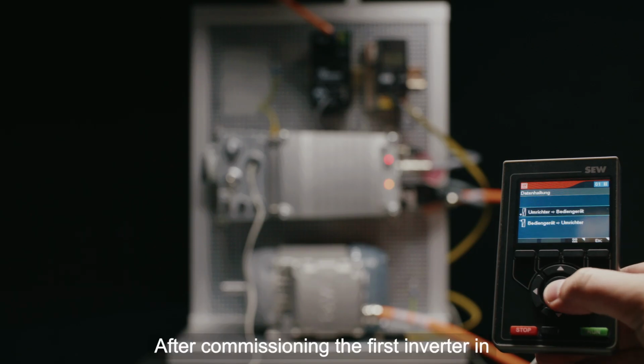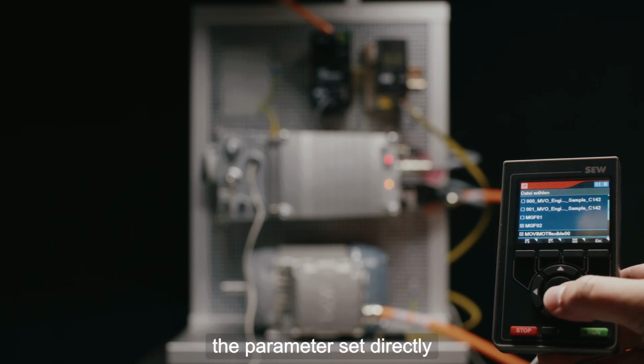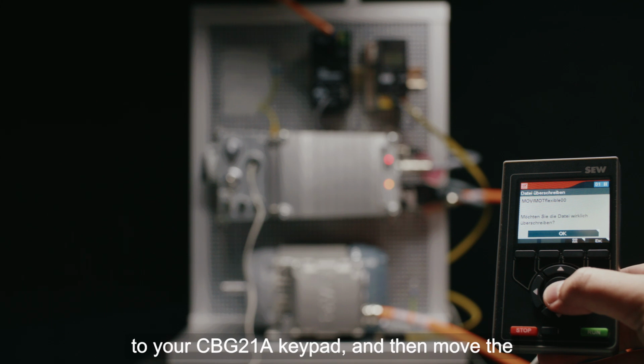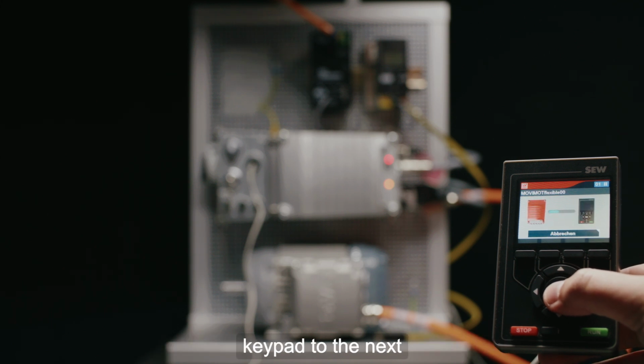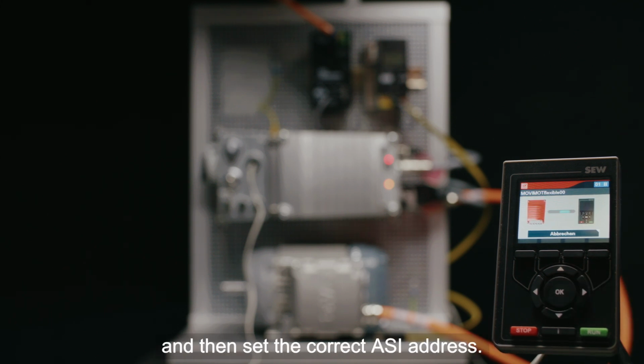After commissioning the first inverter in MOVISUITE, you can export the parameter set directly to your CBG21A keypad, and then move the keypad to the next inverter, import the parameters, and then set the correct ASI address. You can repeat that step for all identical drives.